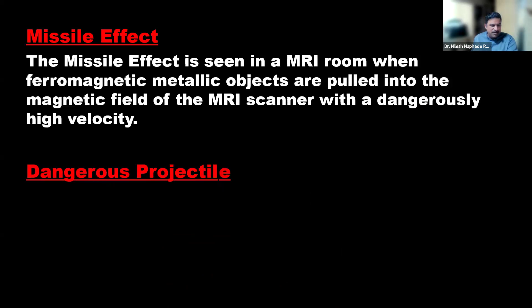It is an effect which comes into play in the MRI room. The missile effect is seen in an MRI room where ferromagnetic metallic objects are pulled into the magnetic field of the MRI scanner with a dangerously high velocity. This pulling of objects into the MRI is called the missile effect, and that gives rise to another term, which is called dangerous projectile.